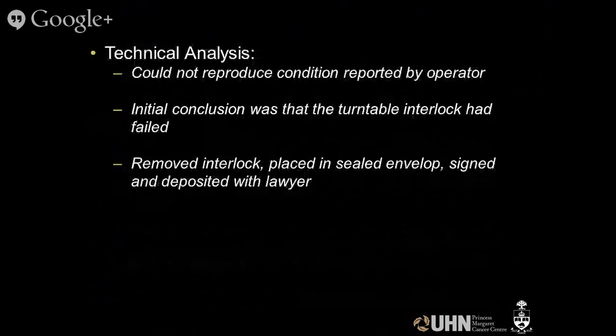So the technical analysis again was that we could not reproduce the error condition. And our conclusion was that the turntable interlock had failed. So we removed the interlock and did the rather odd action, you may think, of placing it in an envelope, sealing it, and giving it to a lawyer.